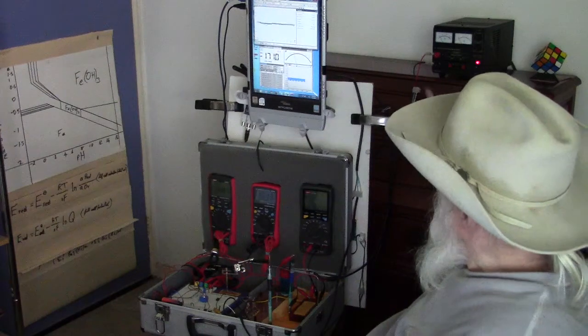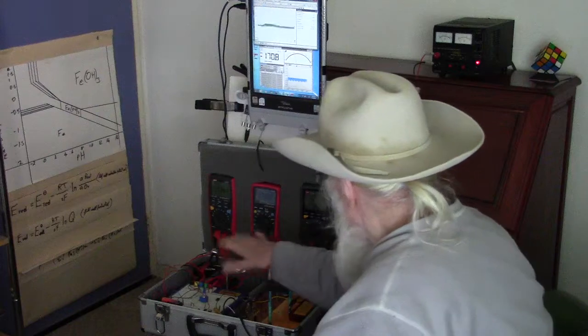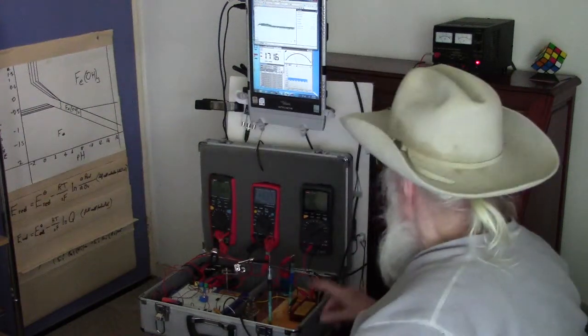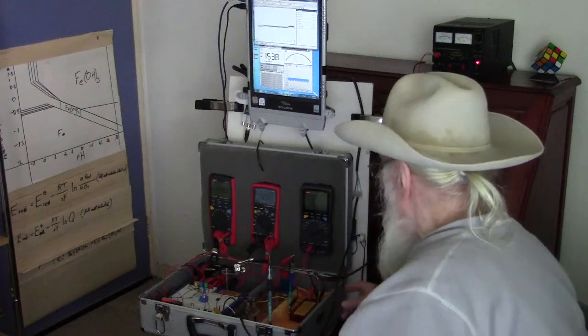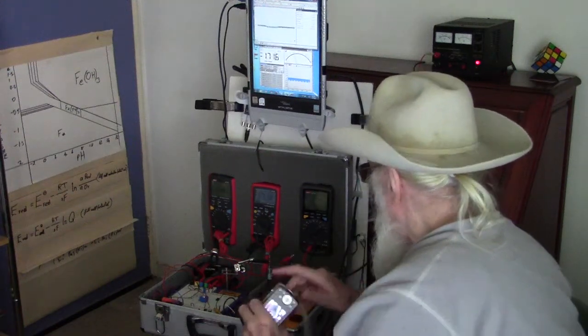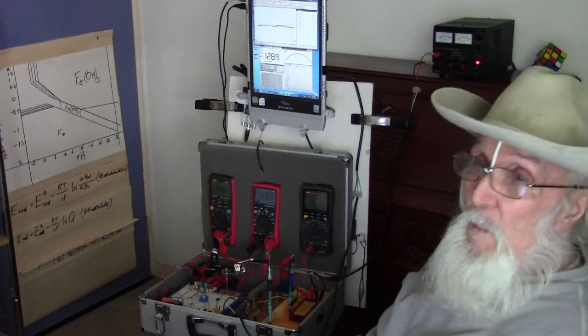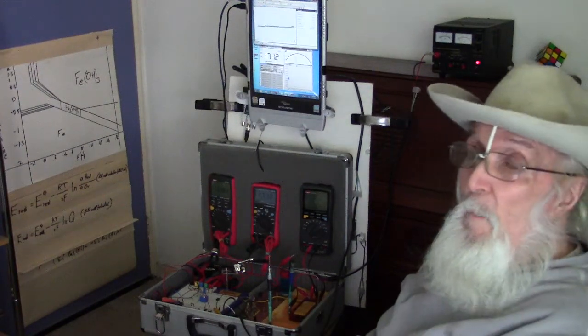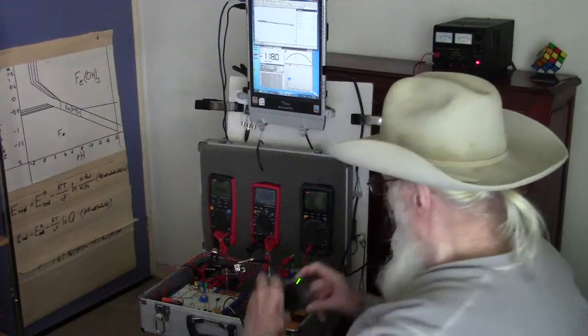And so that is the driving force which is energizing the system, but there's very, very little current demand because of all the resistances and the circuitry of the system. And this is exactly the same in the field with the cathodic protection system. If you had a perfect coating, there would be no current flowing.